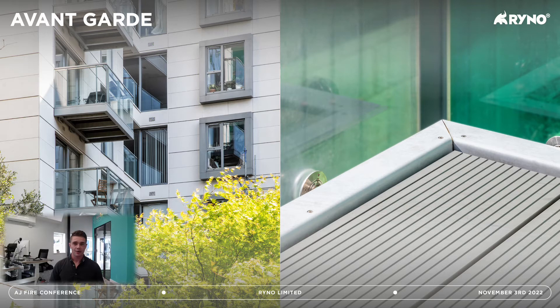With the decking we were then able to look at the different colour options. Colour is a really important one because, as aluminium decking is powder coated, being able to match the colour to the framework of the balcony was a huge advantage. However, different colours are made from different organic material and therefore, from a fire compliance perspective, having that full colour range tested to achieve that minimum fire classification of A2 S1D0 was really important. Balconies form part of the external facade of the building and have to be non-combustible, so that was our number one aim.